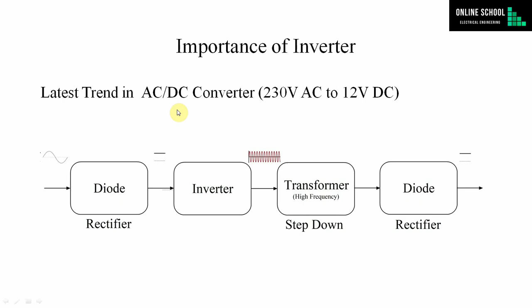If we compare the size and weight gain due to these two additional stages, it will be very small, because the 4 diodes and 4 switches will not add as much weight and size. The major reduction in weight and size is due to the reduction in size of the high frequency transformer. So this is the latest trend in AC-DC converters, and the inverter stage is also there. This is why we observe a reduction in size of power supplies and chargers for the same power rating.